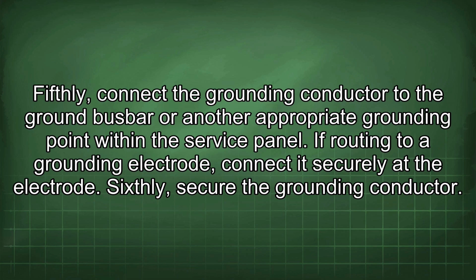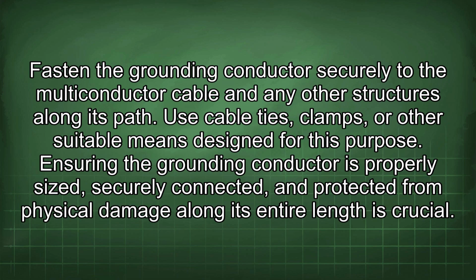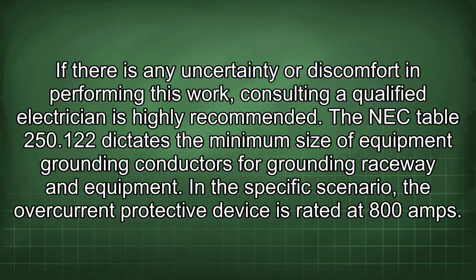Sixthly, secure the grounding conductor. Fasten the grounding conductor securely to the multiconductor cable and any other structures along its path. Use cable ties, clamps, or other suitable means designed for this purpose. Ensuring the grounding conductor is properly sized, securely connected, and protected from physical damage along its entire length is crucial. If there is any uncertainty or discomfort in performing this work, consulting a qualified electrician is highly recommended.